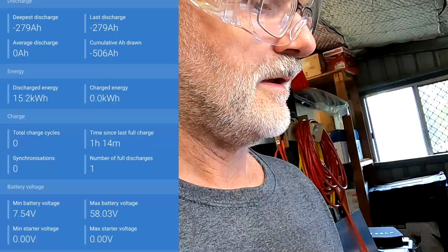What else could you ask for from fake Hithium batteries - rated 280 ampere hours, we got 279 at 200 amps discharge current. That is impressive. From 11.9 to 15.2, that's 3.3 kilowatt hours, right? Yeah, 3.3 kilowatt hours out of this pack at 200 amps. And here we can see the discharge curve now.